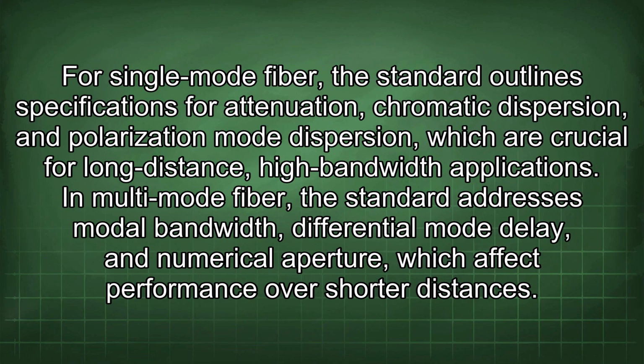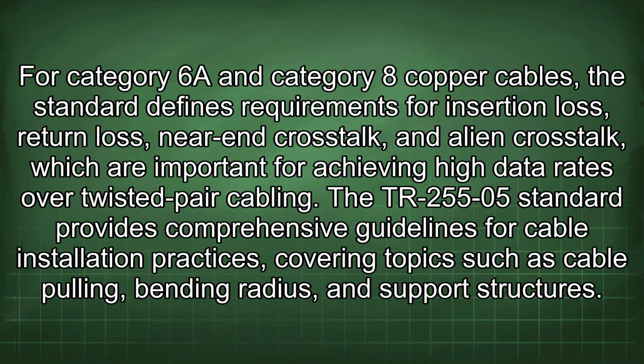For single-mode fiber, the standard outlines specifications for attenuation, chromatic dispersion, and polarization mode dispersion, which are crucial for long-distance high-bandwidth applications. In multi-mode fiber, the standard addresses modal bandwidth, differential mode delay, and numerical aperture, which affect performance over shorter distances. For Category 6 and Category 8 copper cables, the standard defines requirements for insertion loss, return loss, near-end crosstalk, and alien crosstalk, which are important for achieving high data rates over twisted pair cabling.